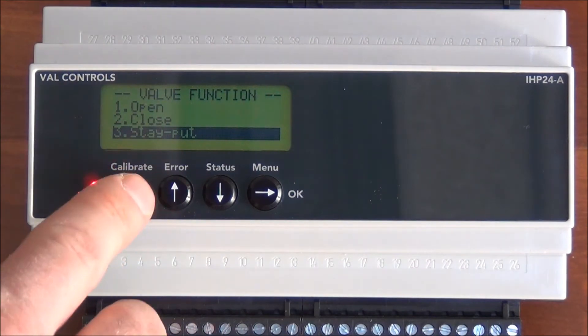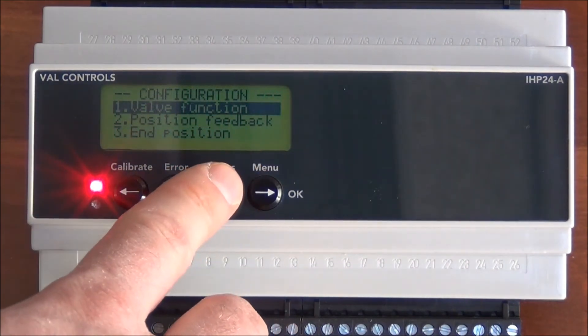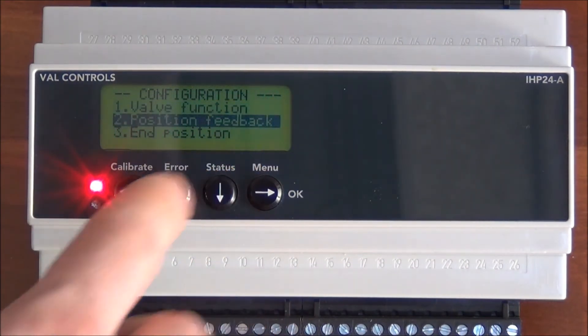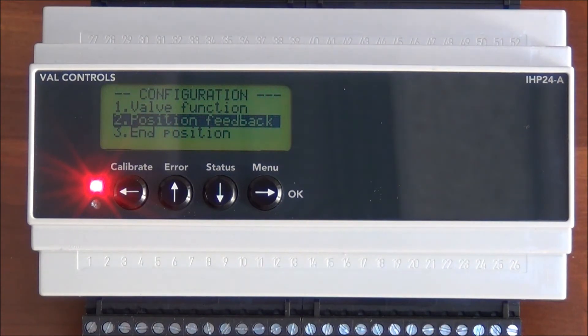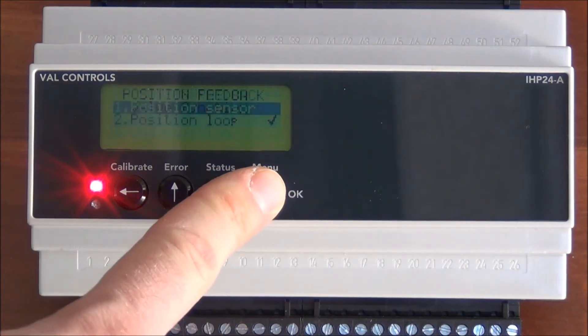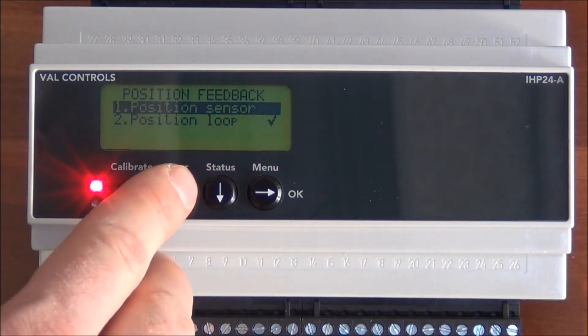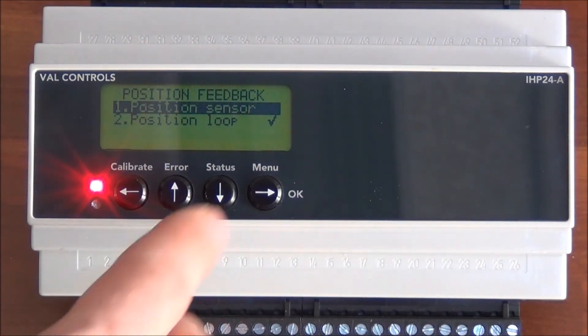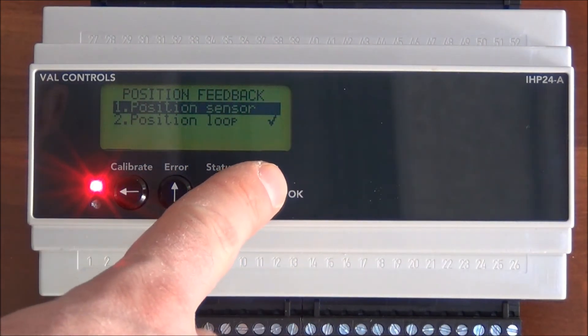Then we configure the valve function. Then we go and configure the position feedback. On the IHP24 you can use a 3-wire potentiometer or a 4-20 milliamp signal. On this one we have a 3-wire potentiometer so I'll choose the position sensor.